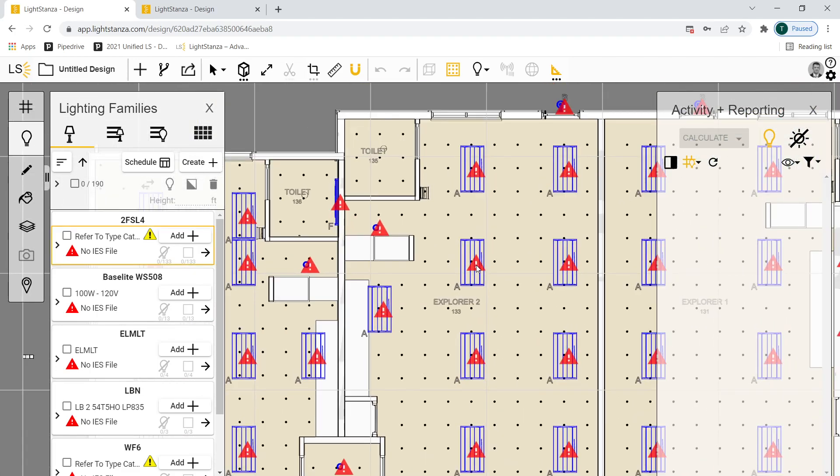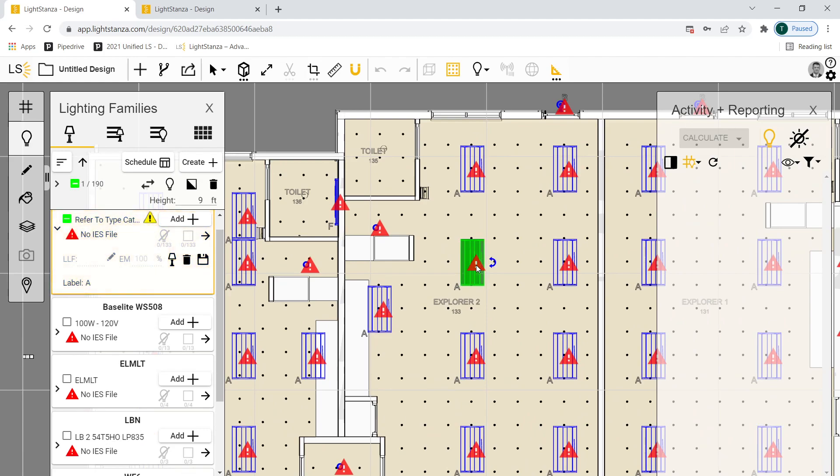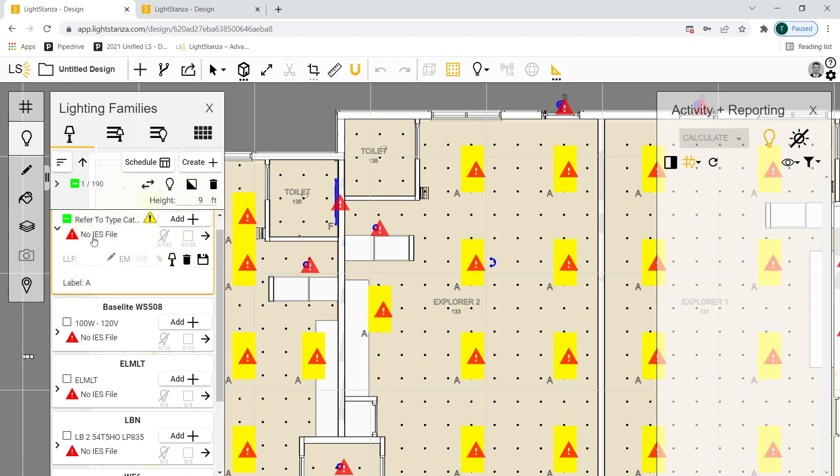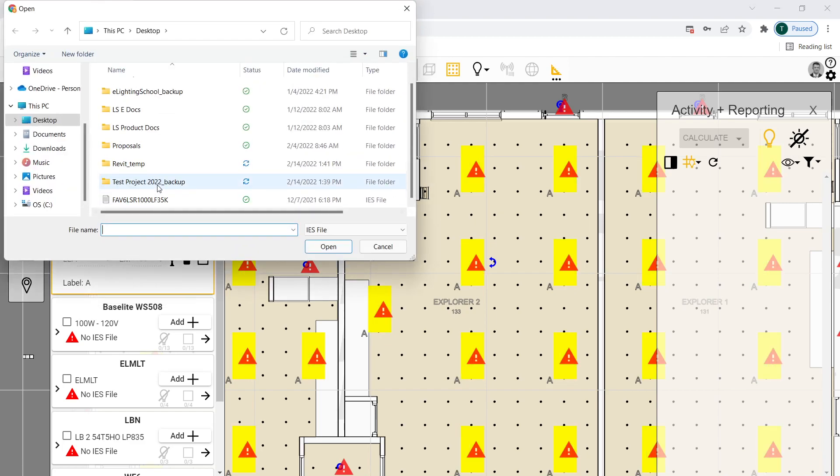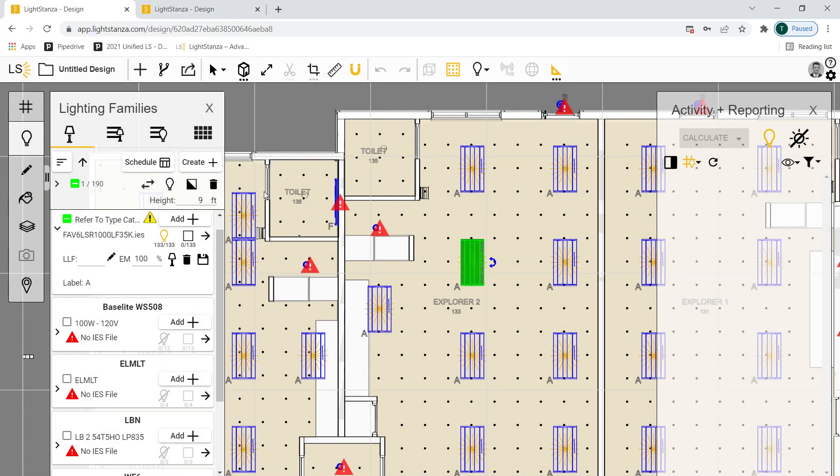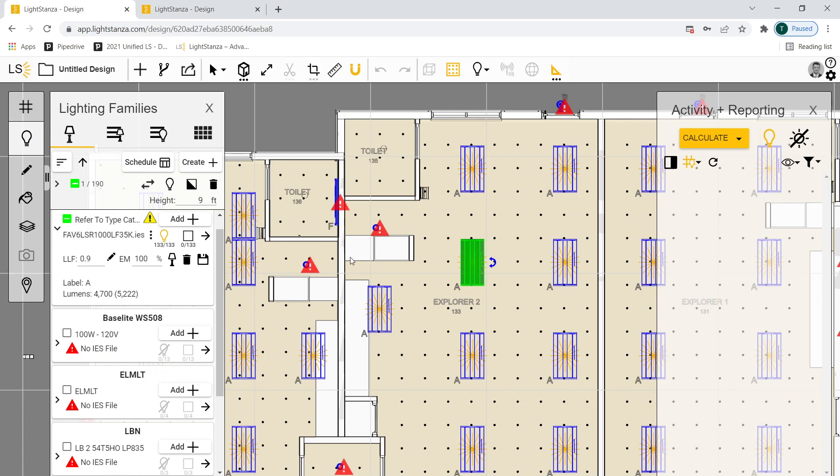This is just saying that there isn't an IES file associated with this light fixture. If I select it over here, it says no IES file. If I pick that, I can upload one off my desktop or from anywhere else. Or you can build an IES file library for fixtures that you commonly use. For this demo, I'll just pick one on my desktop. And now you can see that that IES file is assigned to those light fixtures. So if there were IES files assigned to these in Revit, they would have come into Light Stanza.